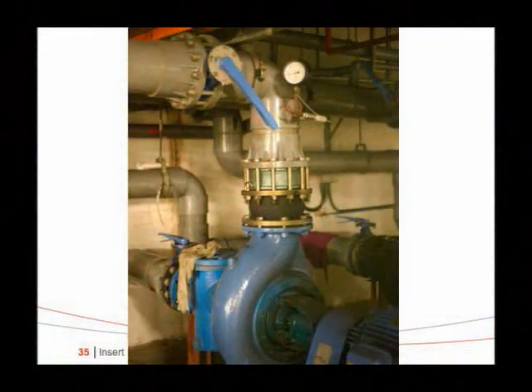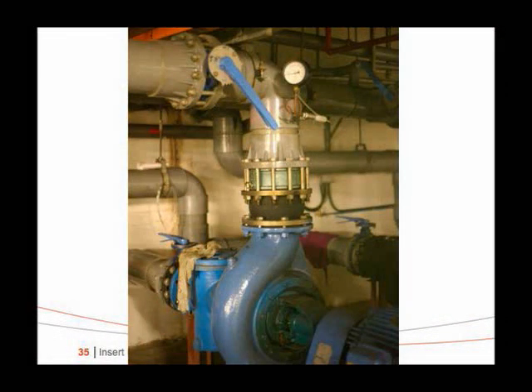Sticking with the water side, just before I came, I went to a big shopping mall to do something, and this was very interesting. Domestic water pumping. One normally doesn't think of this as being a big user, but the pumps, I think, were originally 100-something, 125 horse or 150 horse. And of course, they are so oversized that they have to throttle the discharge.